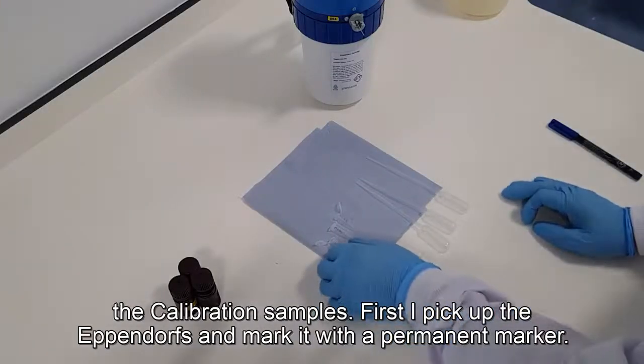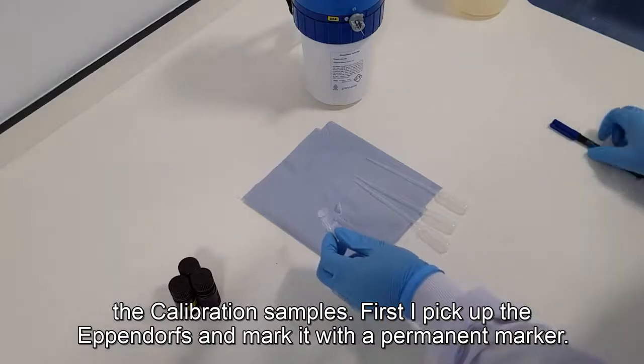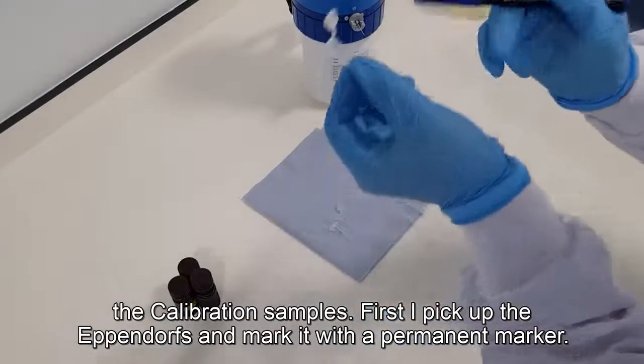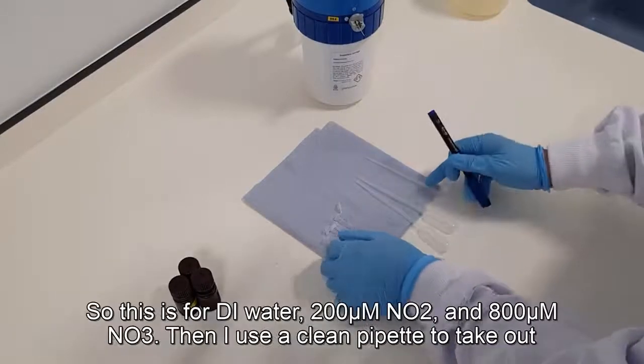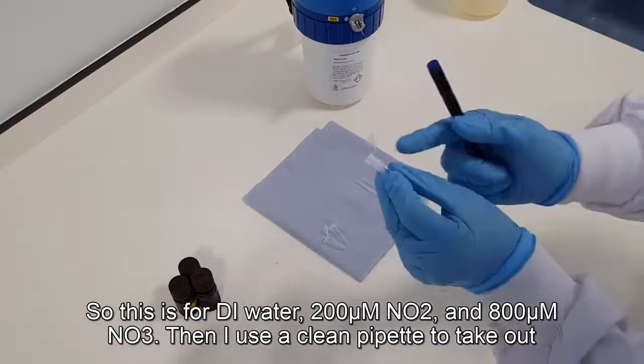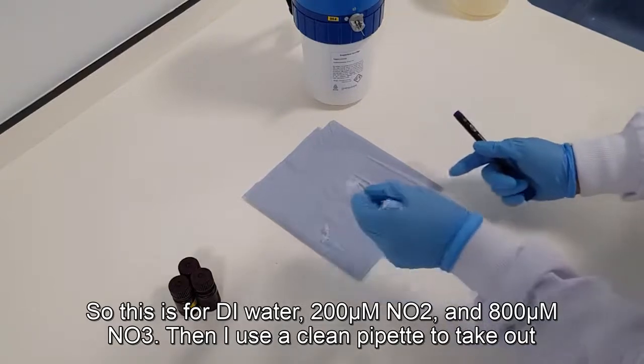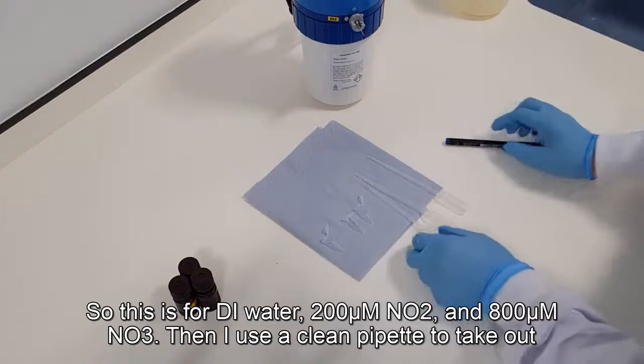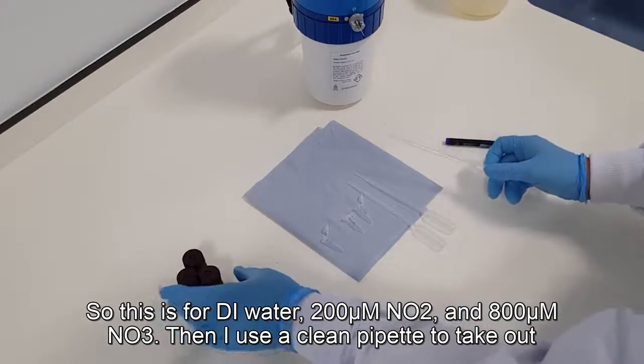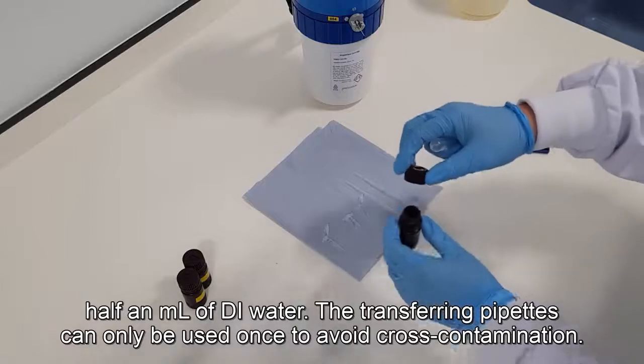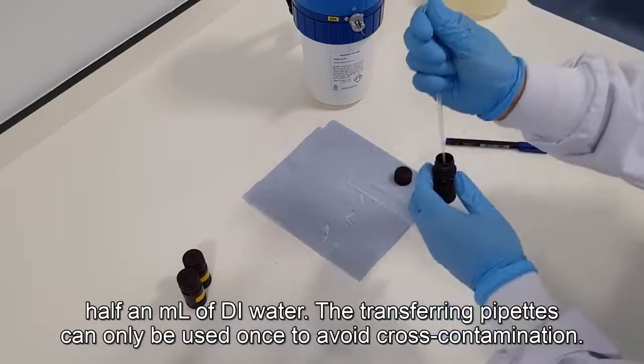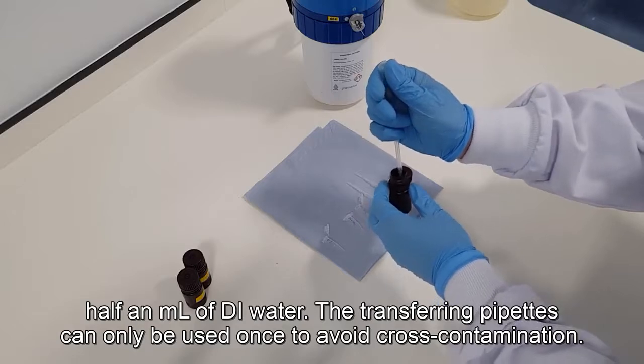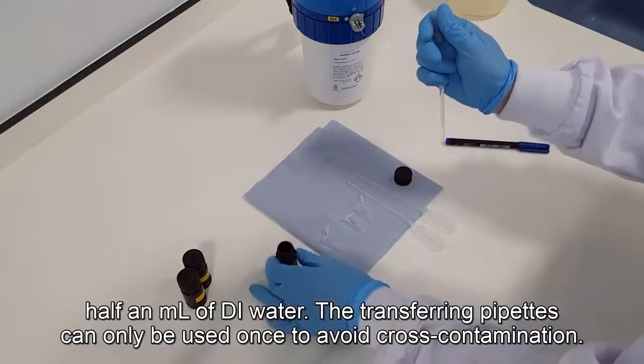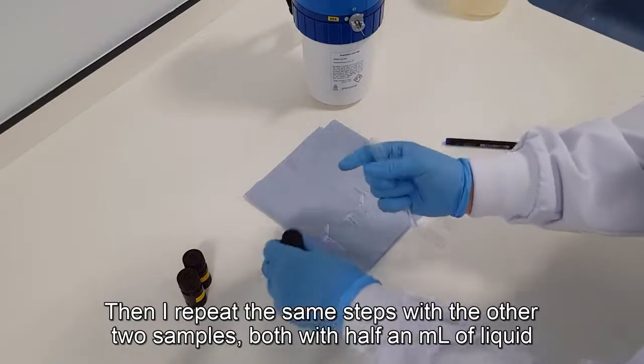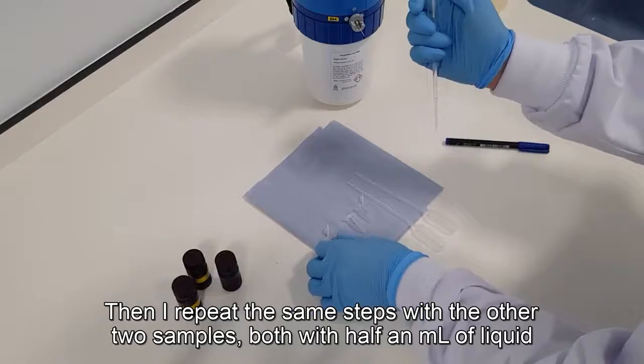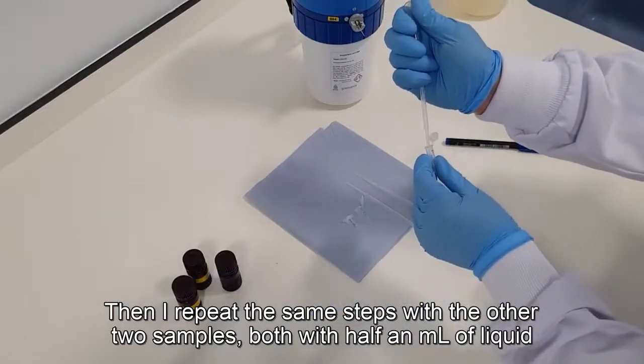Now let's start to prepare the calibration samples. First, I pick up the Eppendorfs and mark it with a permanent marker. So this is for DI water, this is for 200 micromolar NO2, and that is for 800 micromolar NO3. Then I use a clean pipette to take out half a milliliter of DI water. The transferring pipette can only be used once to avoid cross-contamination. Then I repeat the same steps with the other two samples, both with half a milliliter of liquid samples.